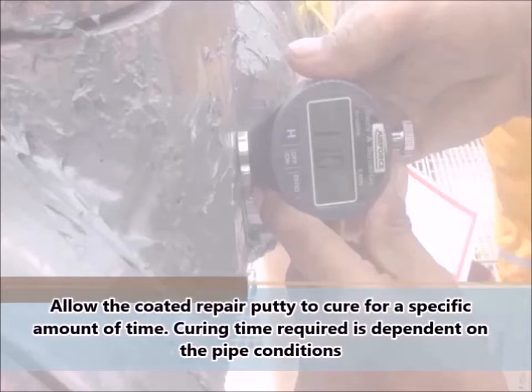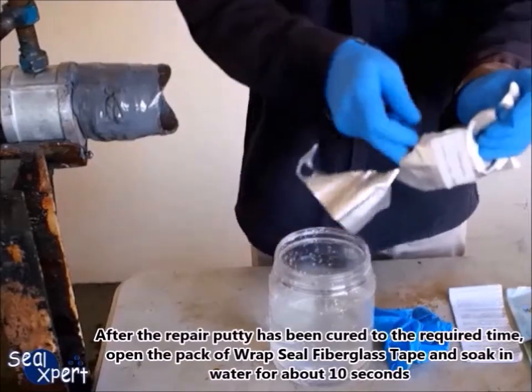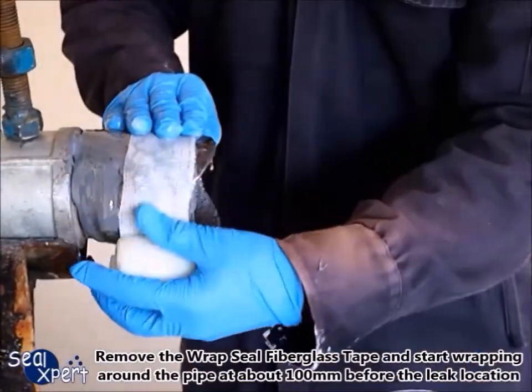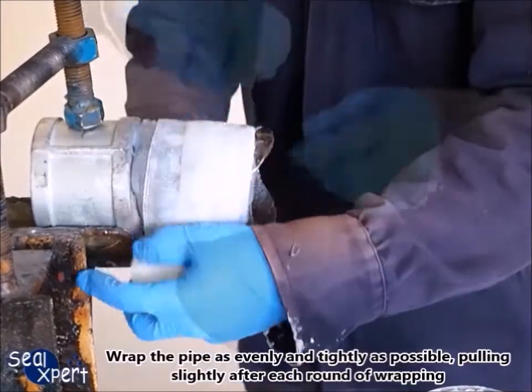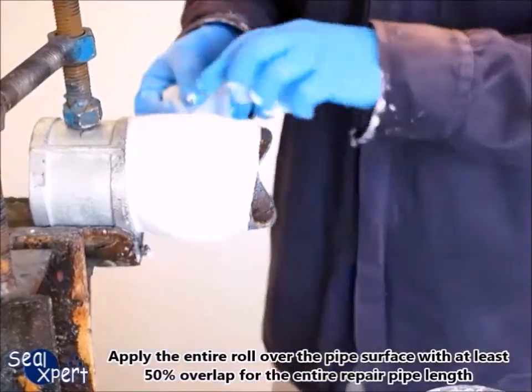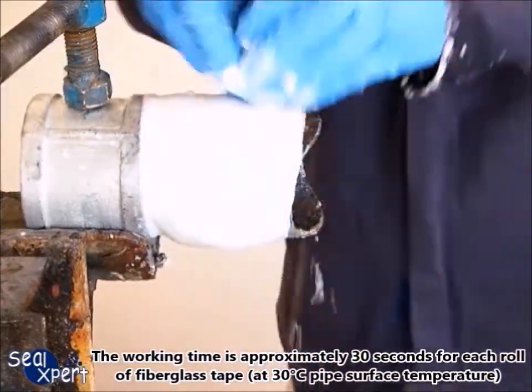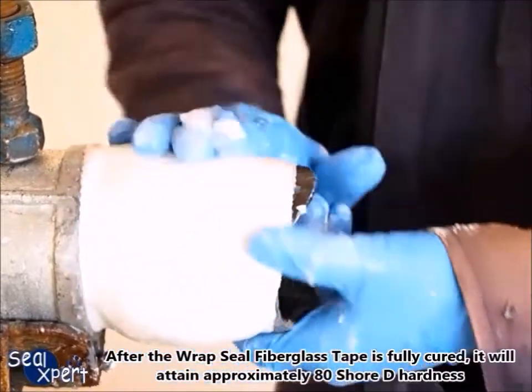Allow the coated repair putty to cure for a specific amount of time — curing time required is dependent on the pipe conditions. After the repair putty has cured to the required time, open the pack of Wrap Seal fiberglass tape and soak in water for about 10 seconds, squeezing the tape to ensure it is fully immersed. Remove the fiberglass tape and start wrapping around the pipe at about 100 millimeters before the leak location. Wrap the pipe as evenly and tightly as possible, pulling slightly after each round. Apply the entire roll with at least 50% overlap for the entire repair pipe length. The working time is approximately 30 seconds per roll at 30 degrees Celsius pipe surface temperature. After fully cured, it will attain approximately 80 Shore D hardness.